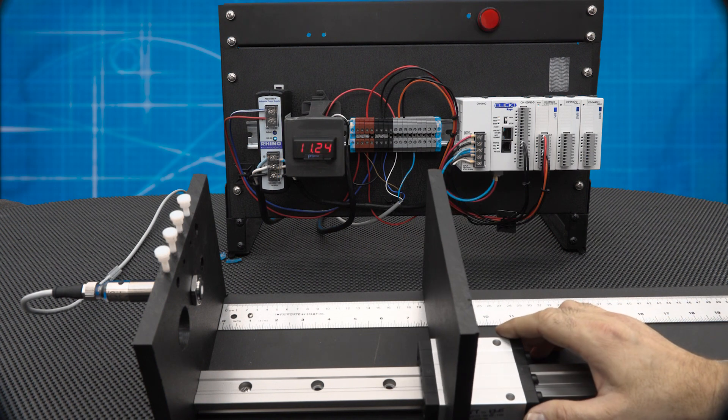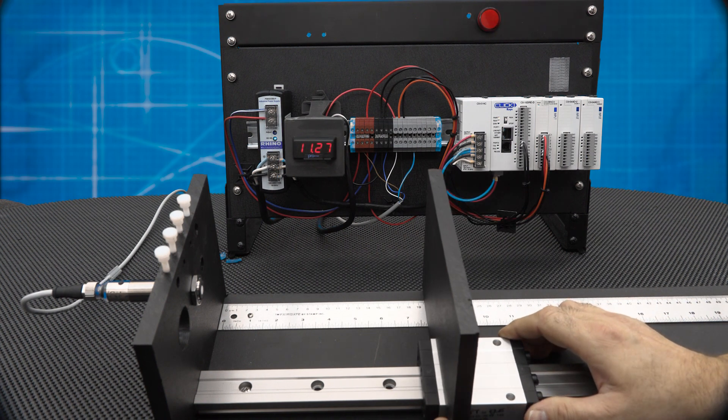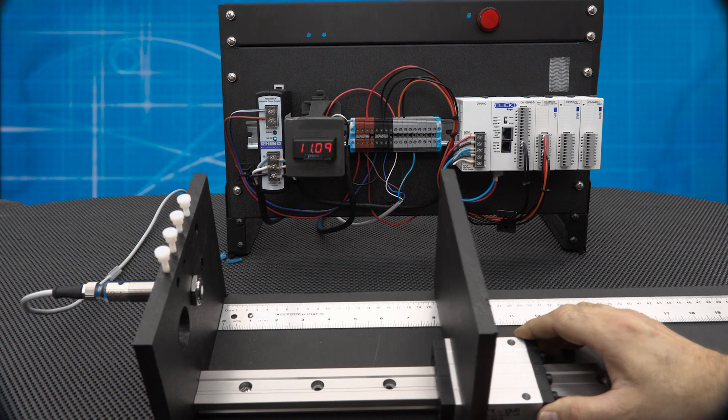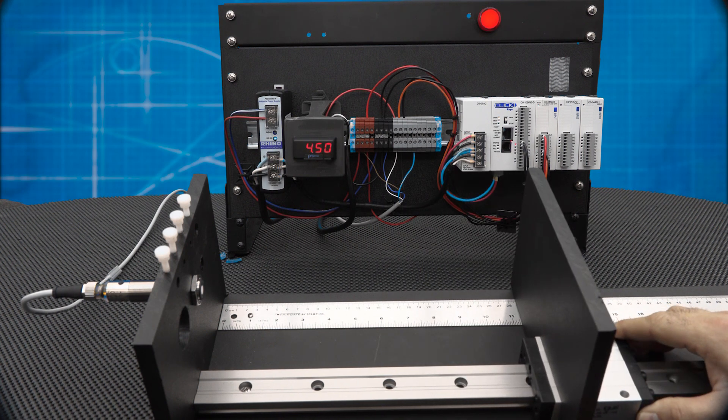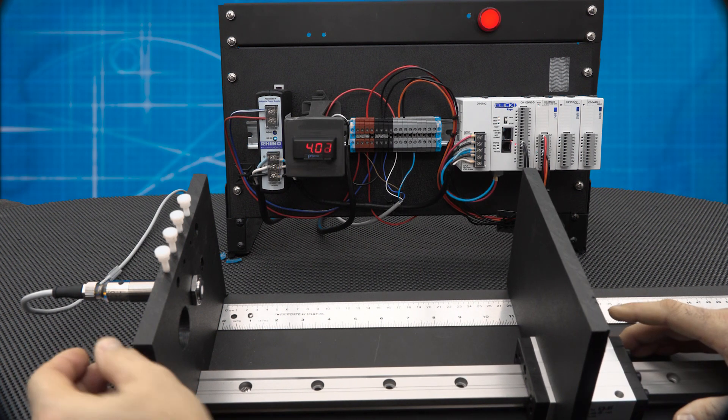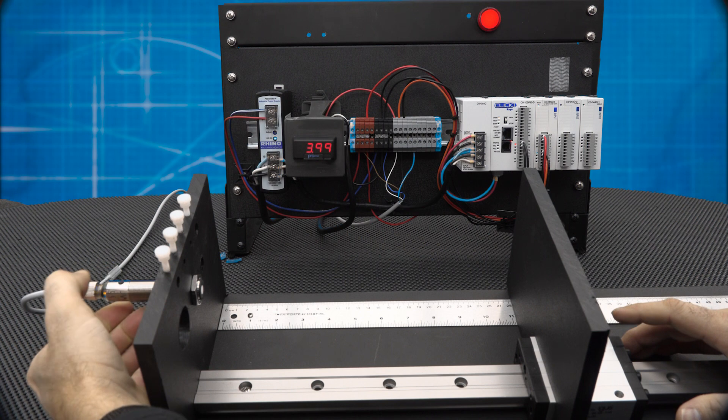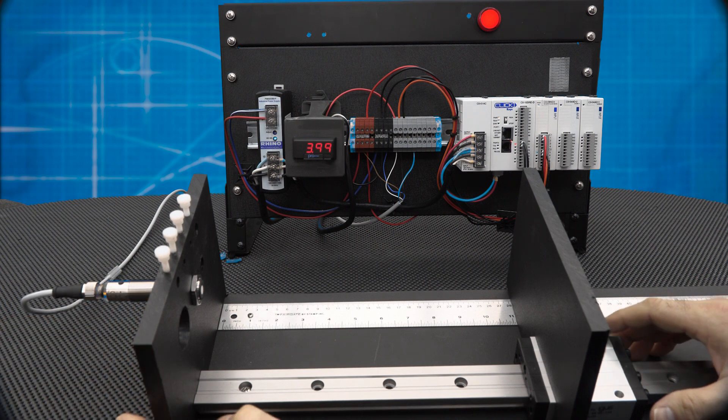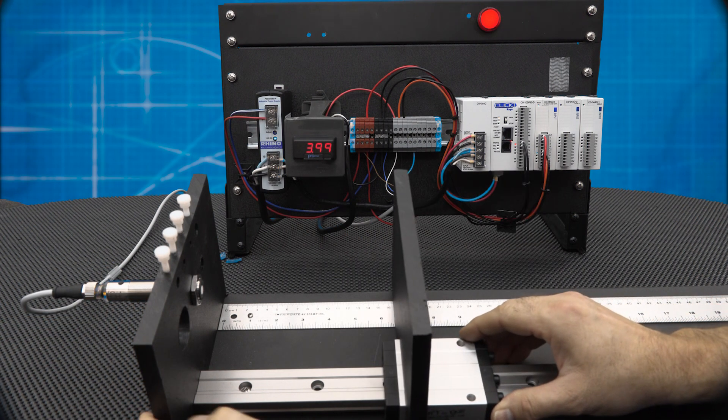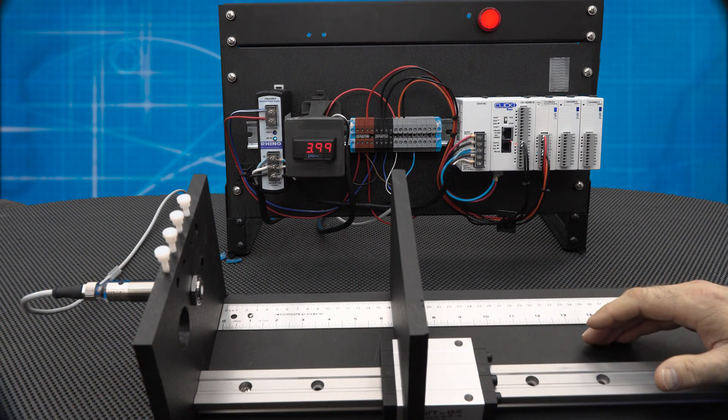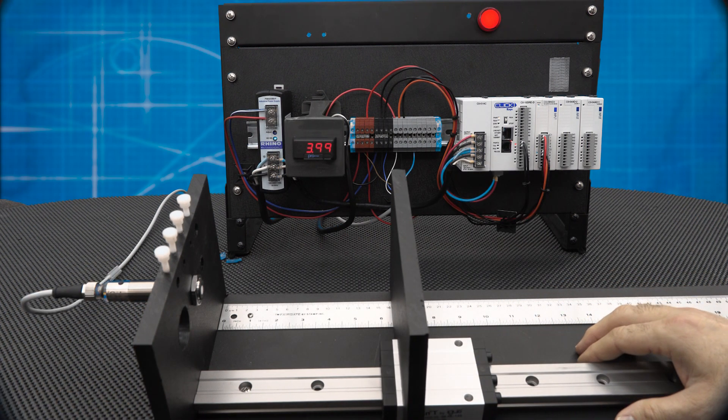The sensor will remain in window mode configuration until we reprogram it for a new configuration. We can easily change the target distances and whether we want a positive slope analog with normally open discrete output or negative slope analog with normally closed discrete output.